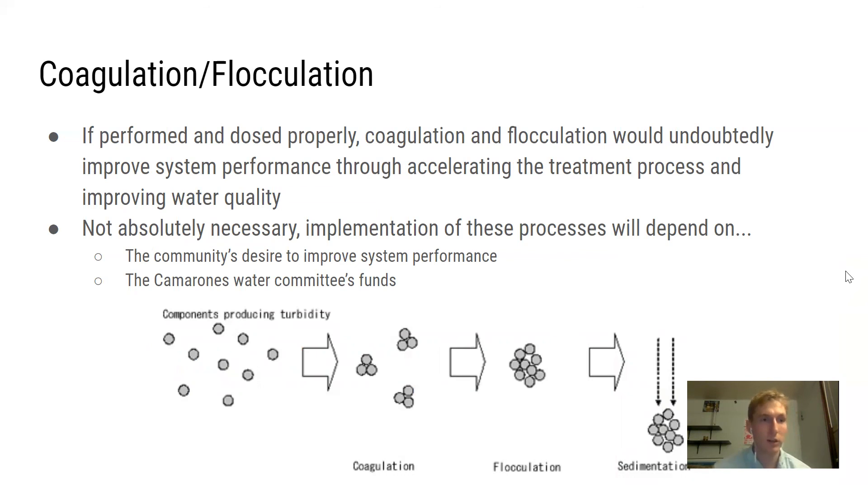So then we go back to coagulation and flocculation. Like I said, we did dismiss this for the Camarones water project for now. We just don't think it's necessary and would require more maintenance from the community. But again, this possibly could be used to help with the vanadium problem or even problems with the sedimentation. If our sedimentation basin isn't quite performing well enough for the community's needs, this could be another added process of coagulation and then flocculation settling for solids and metals and things. Definitely something we will consider for the future as we monitor this project.